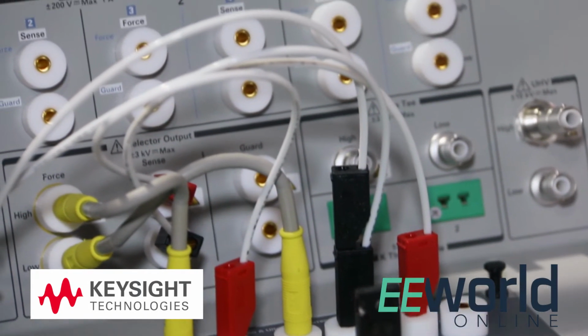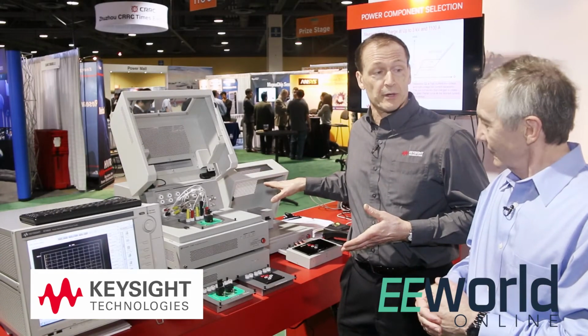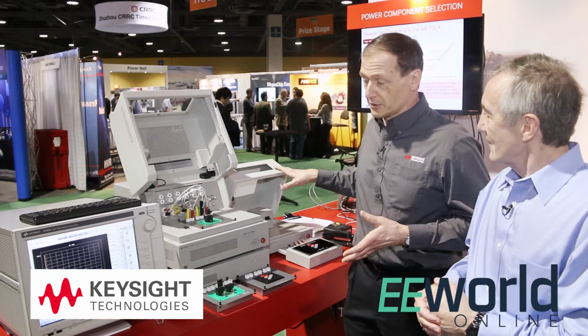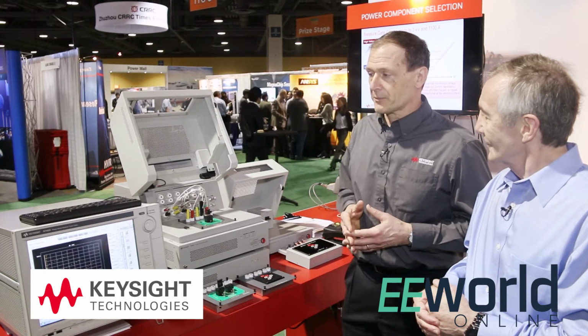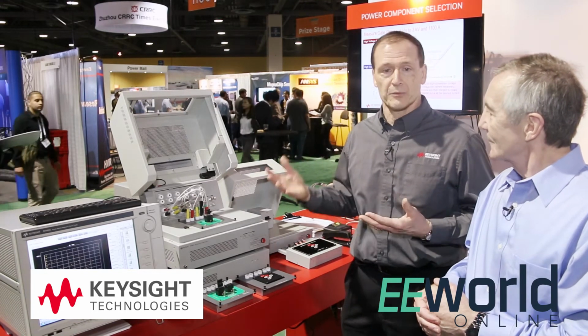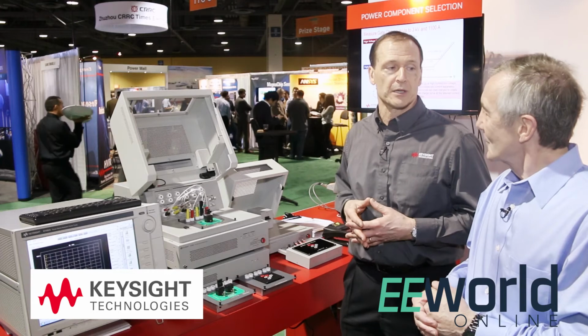Again, we can also measure even negative threshold devices. We can measure the capacitance on those very easily with our fixturing, very simple to do. So the wide bandgap stuff for us is actually quite easy to do. Again, we can go to the high voltages and currents that those devices require as well.